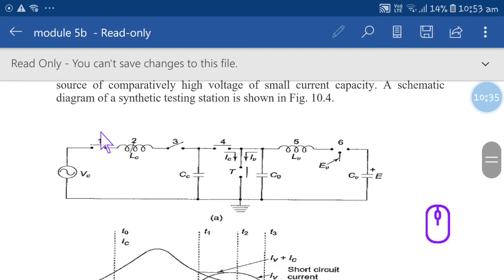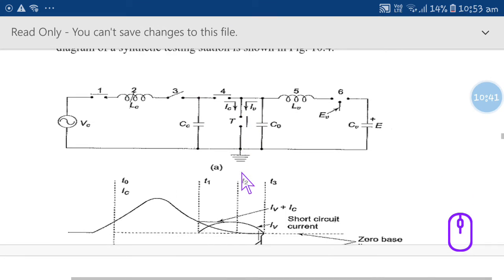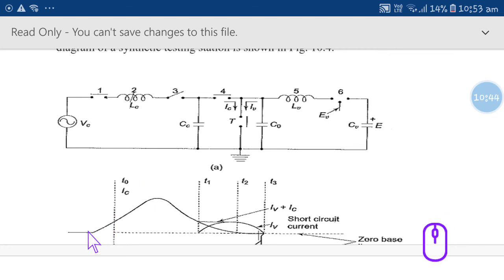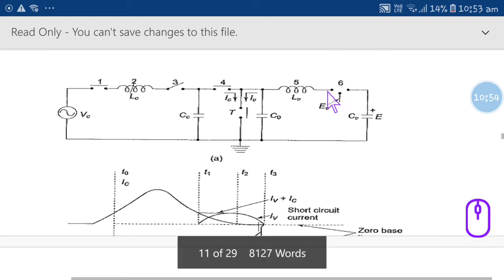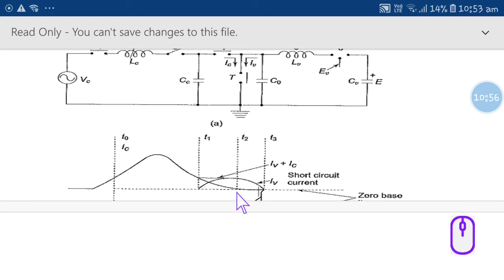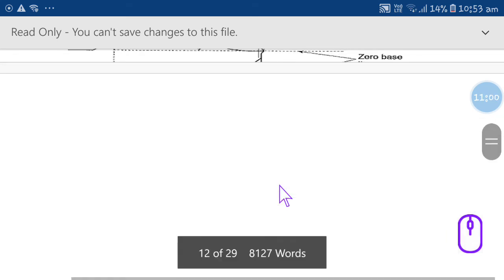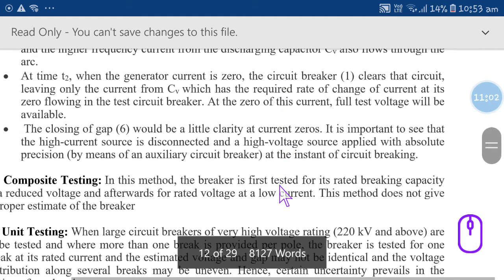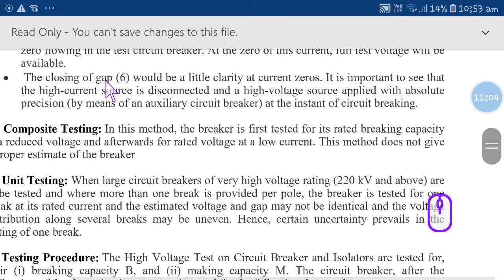This is 1. First this 3 as well as this T will operate and be closed, and current will pass. So this starts from T0. Here the current will flow and rise. Maximum it will be, then it will come down at the T1 position, and next will be T2. Last will be T3, and the sixth switch will be closed depending upon operation. Once a short circuit has happened, it can withstand it. Afterwards the current has to come to 0. This is the short circuit test. All these things are explained properly in this.